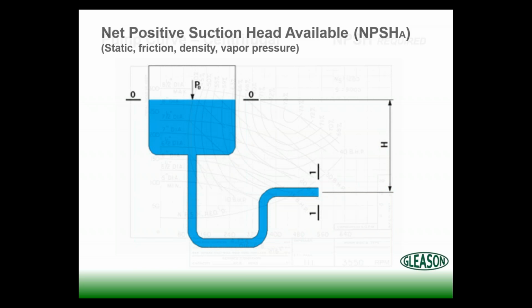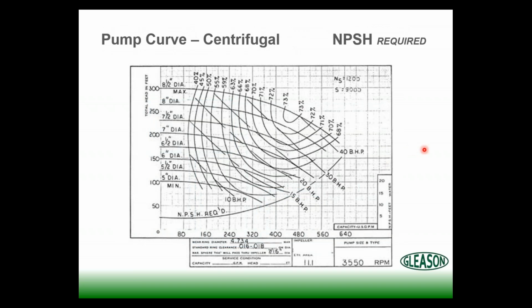from forming. Every pump you've got on campus, every centrifugal pump, comes with a curve that spells out how much net positive suction head is required. This inverse curve here, by the way, every curve is unique to a manufacturer, to a model number, to an RPM, different impeller trims, different pressures and flow rates. So every pump you've got, please pay attention to that net positive suction head required.